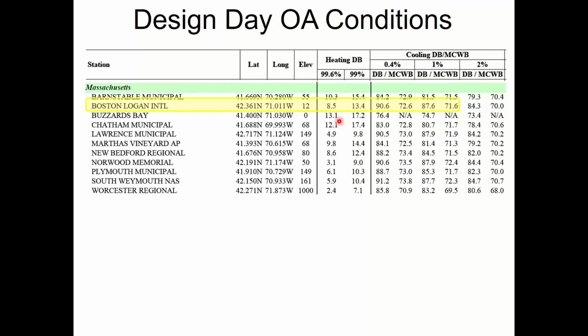Does it ever get down to -3? Sure, it gets down to -3 once in a while, but that's not a normal scenario, and hence I'm not going to design for that. I'm going to design for this statistical worst time. So 8 degrees is my heating design here. I can be less conservative, go to 13, but nobody ever does that.